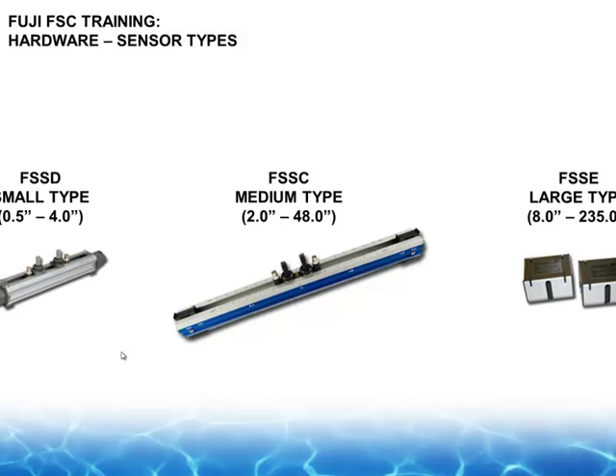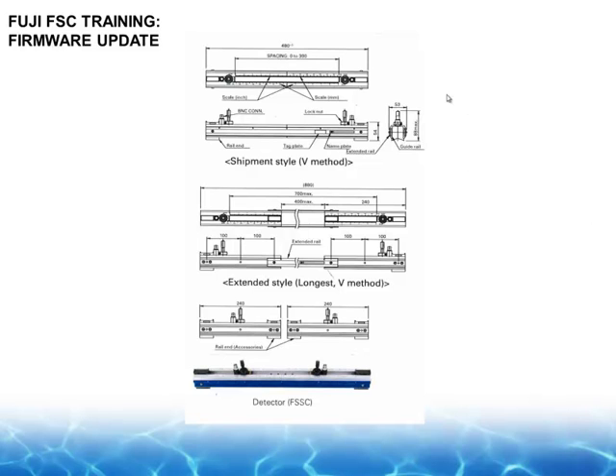Pictures of the transducer, here we go. The FSSD, half to 4 inches, looks just like it did before. BNC to LEMO cables. Now the new FSSC looks like the other old transducer, actually looks a lot like the old FLD11. BNC connectors, so BNC to LEMO, they're not potted like they were with the FSG31. But look at this blue bar. Pray tell, what could that mean? We'll see that in a picture next. And here's the big blocks for the half megahertz transducer. Here's your transducer. Still fits in your suitcase there with no additional modifications. But look at this.